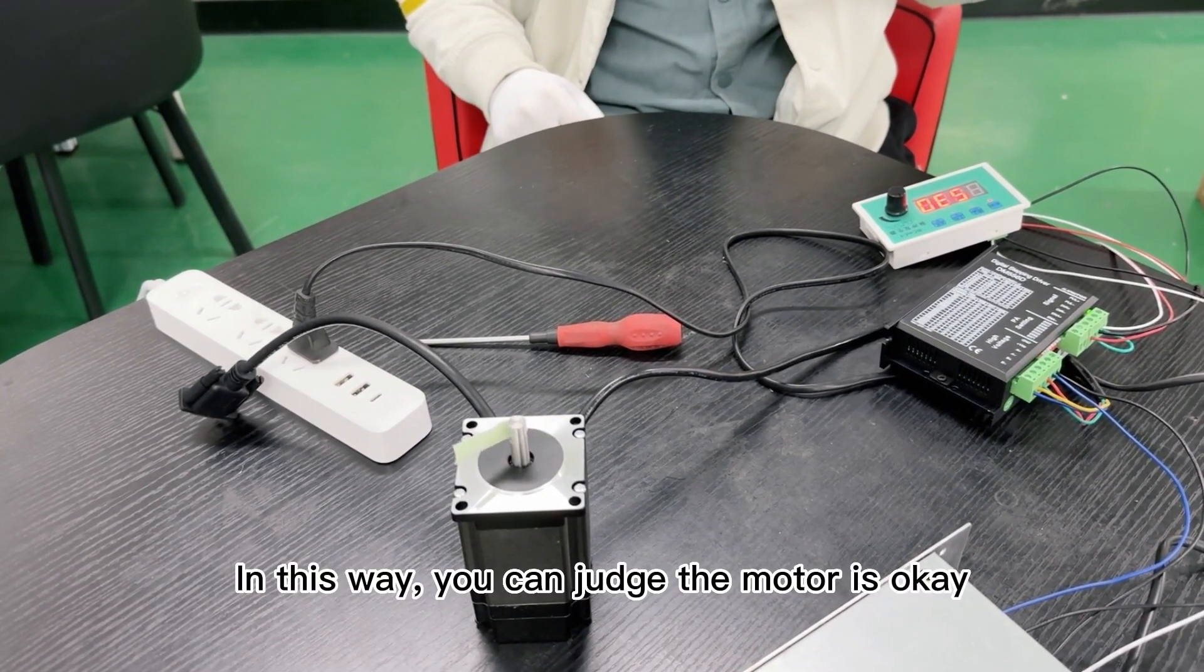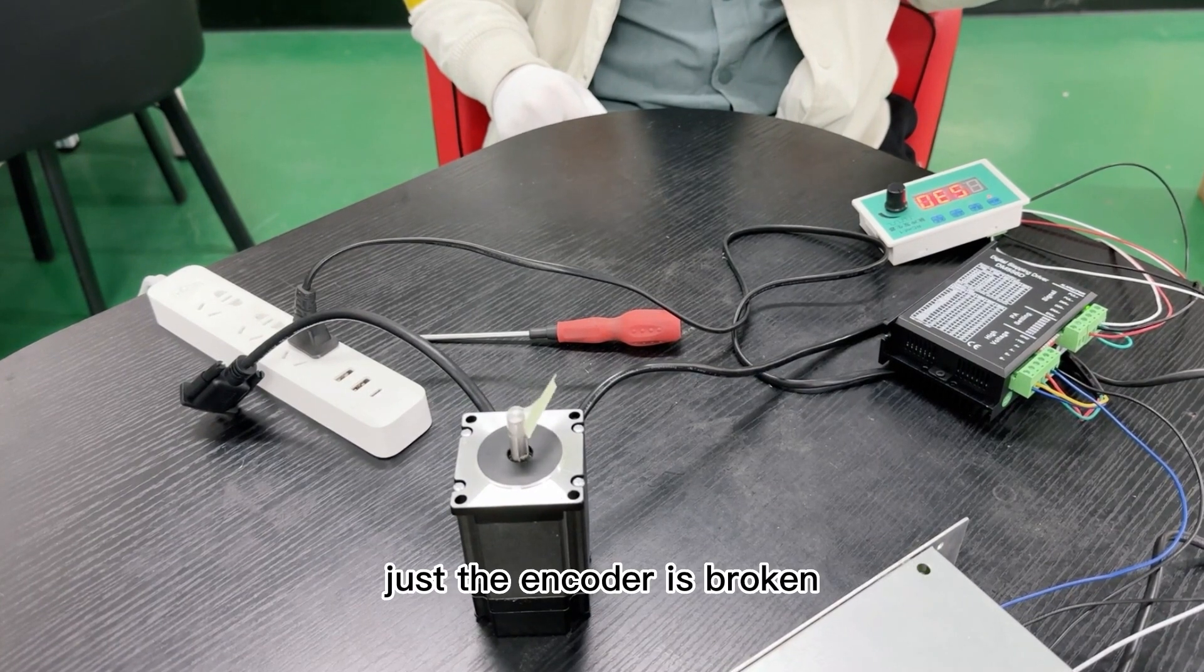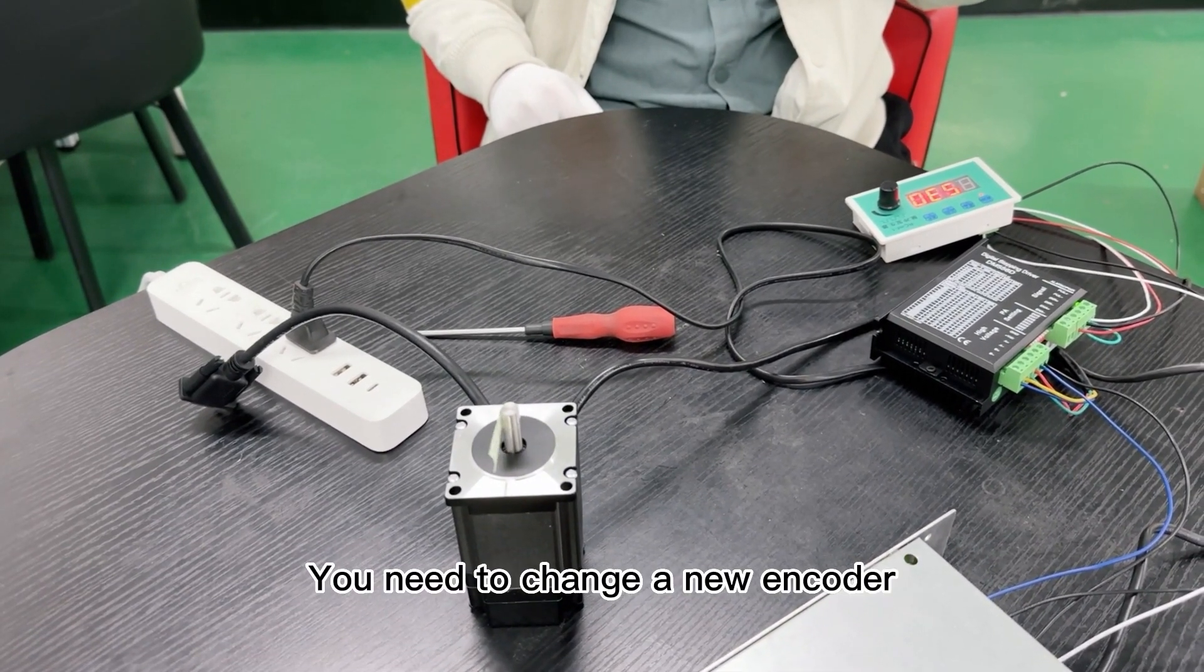In this way, you can judge the motor is okay, just the encoder is broken. You need to change a new encoder for the closed loop driver.